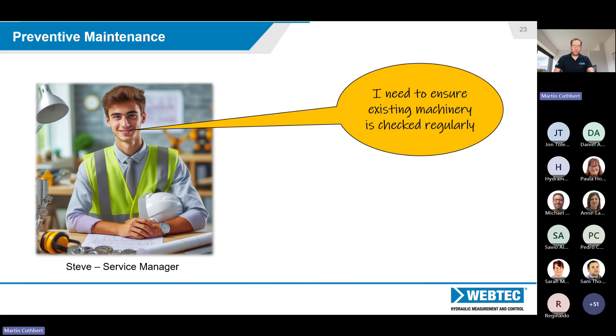So in that example, you can see there the time base could be 10 years, could be a long time. The performance level, typically you would look at volumetric efficiency and say, okay, at what point do we say that the pump is now no longer efficient enough that we need to replace it? If we do it too early, let's say after 5 years, there's a potential there that we've wasted 4 years of its life. If we do it too late, let's say after 10.5 years or 11 years, it may already have blown up. So where's the ideal point?